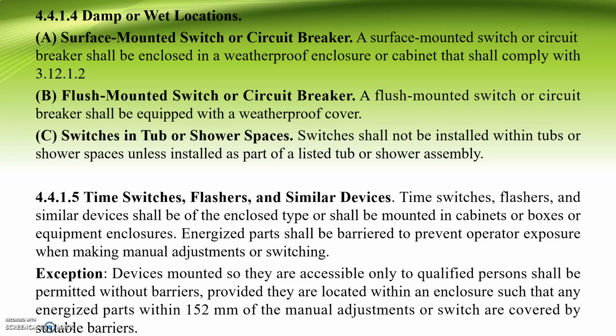Exception: devices mounted so they are accessible only to qualified persons shall be permitted without barriers, provided they are located within an enclosure such that any energized parts within 152 mm of the manual adjustments or switch are covered by suitable barriers.